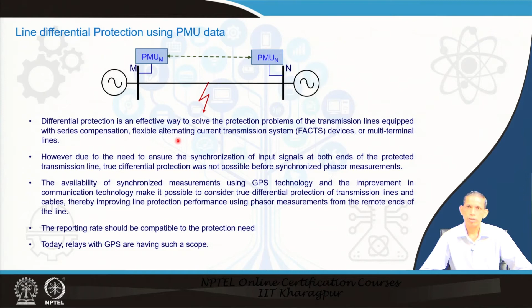So, synchronized measurements give us I1 minus I2, otherwise you cannot do it, as already pointed out in the concept of synchrophasor. The only thing is that if the reporting rate and the associated latency are compatible with this particular protection requirement, then this can be directly applied. The advantage of such differential protection is that if the line has a capacitor, FACTS devices or is a multi-terminal line, then we can exploit such a facility for accurate protection schemes. And multiple lines may be emanating at different points. So, in that case the best solution will be differential protection, and if you go for synchronized data, it becomes easier and more accurate.